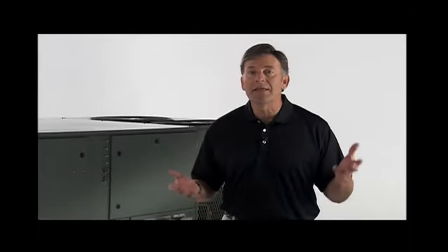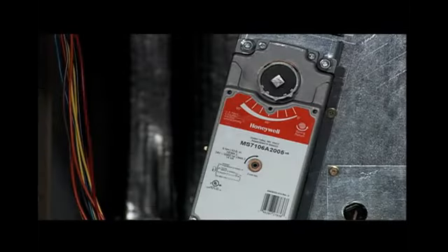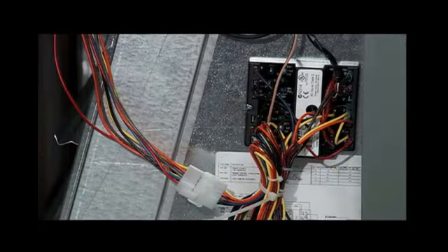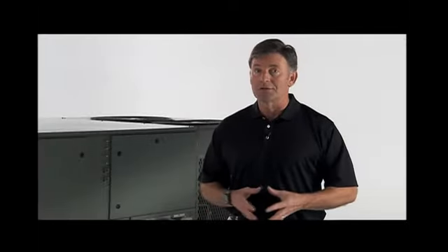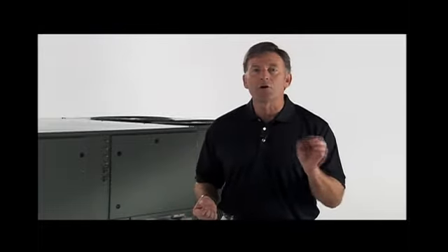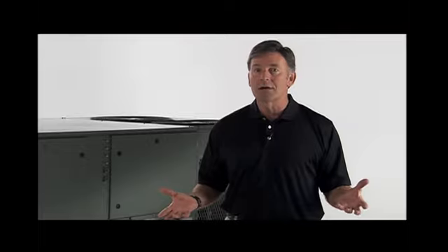Each compressor and circuit is independent for built-in redundancy, and each circuit is clearly marked throughout the system. Each unit comes standard with liquid-line filter dryer. The condenser fan motor can easily be accessed and maintained through the outdoor compartment. The polarized plug connection allows the motor to be changed quickly and eliminates the need to snake wires through the unit. The outdoor coil uses the latest enhanced fin design for the most effective method of heat transfer. The outdoor coil is protected by optional louvered panels which allow unobstructed airflow while protecting the unit from both Mother Nature and vandalism. Louvered panels are standard on 12.5 ton models.